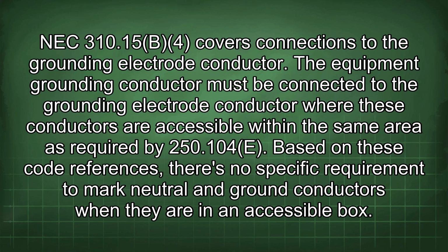NEC 310.15(B)(4) covers connections to the grounding electrode conductor. The equipment grounding conductor must be connected to the grounding electrode conductor where these conductors are accessible within the same area, as required by 250.104(E).